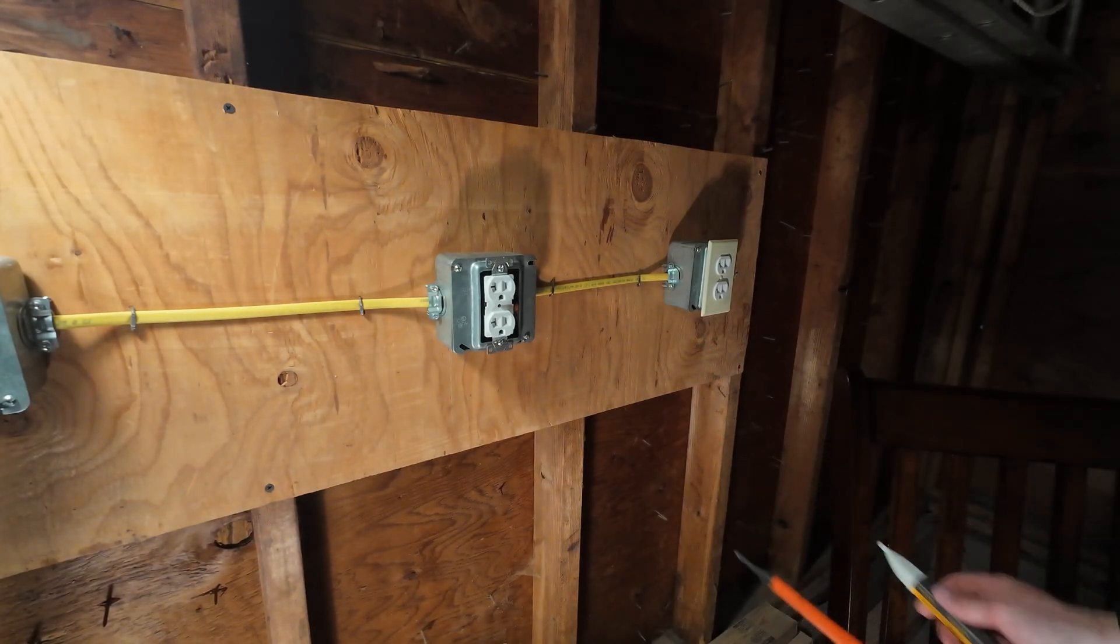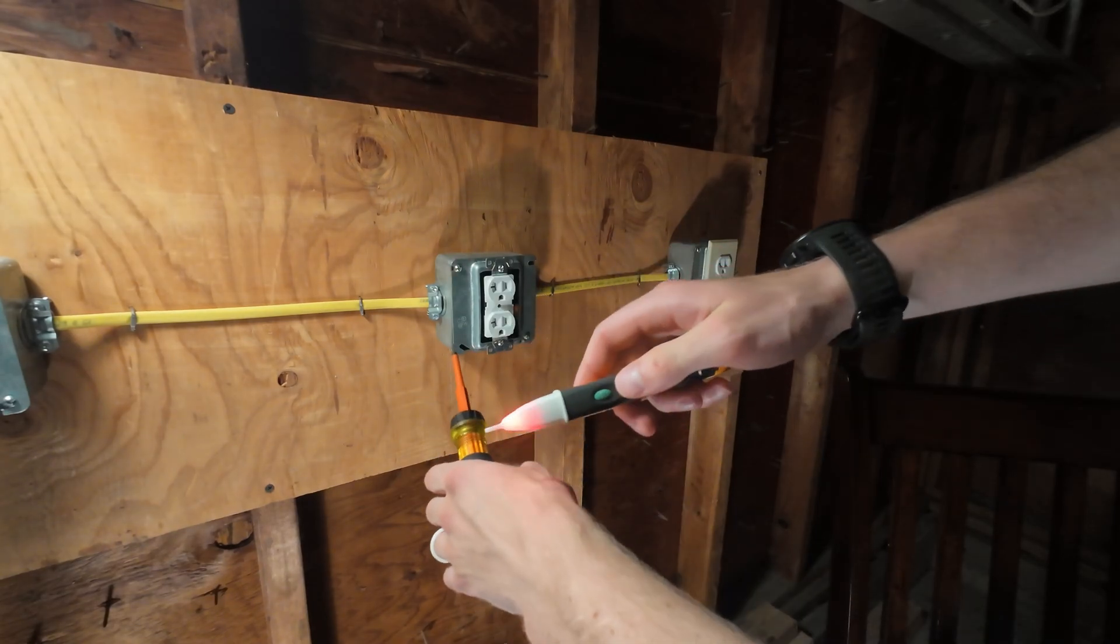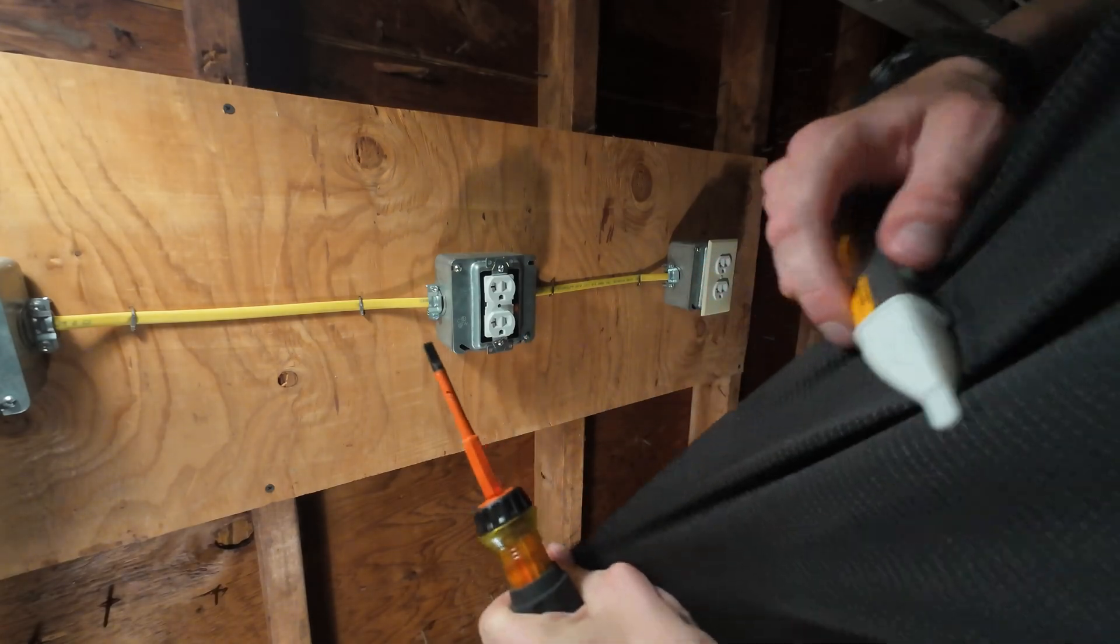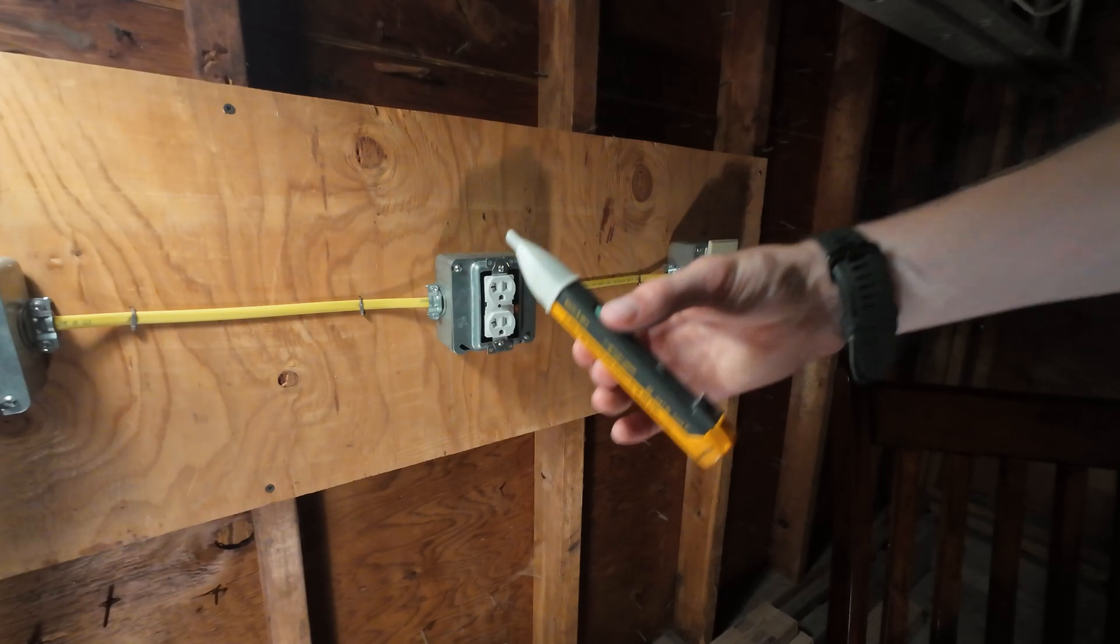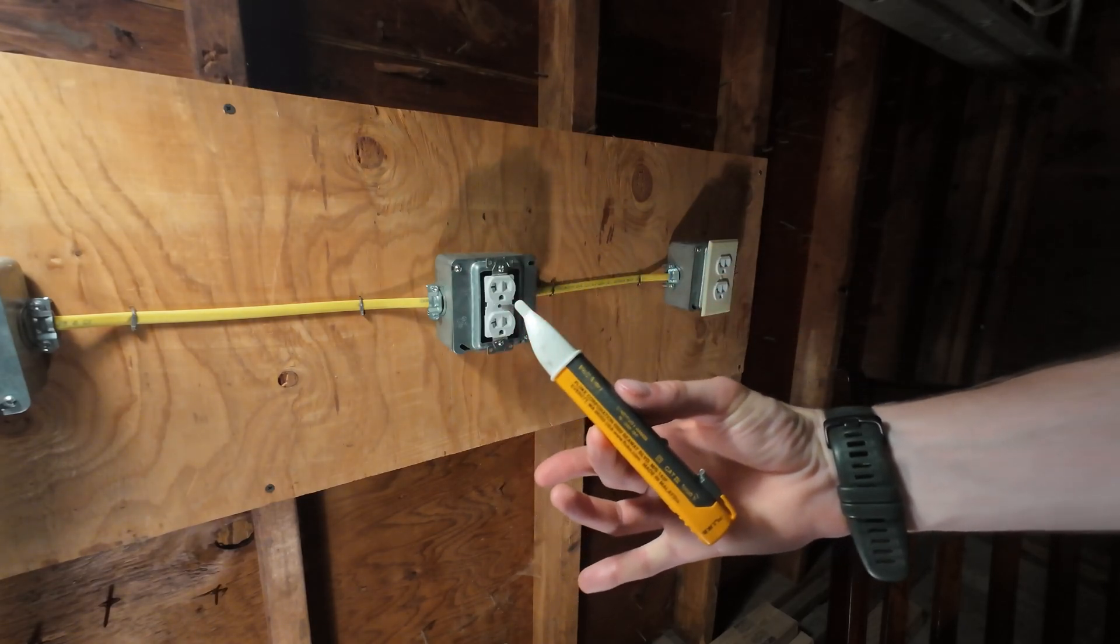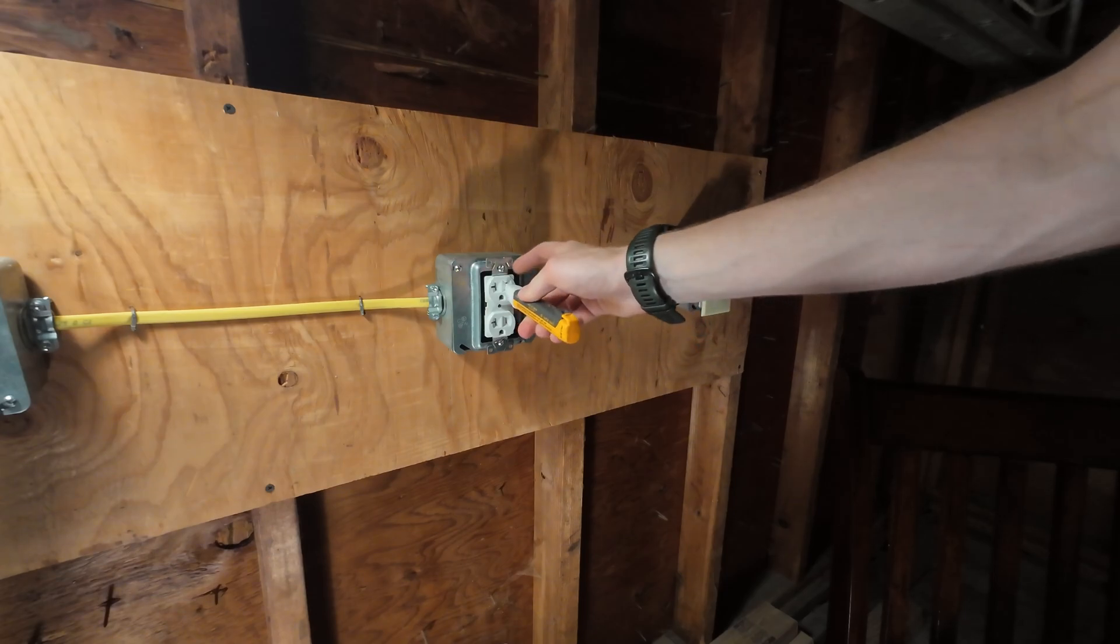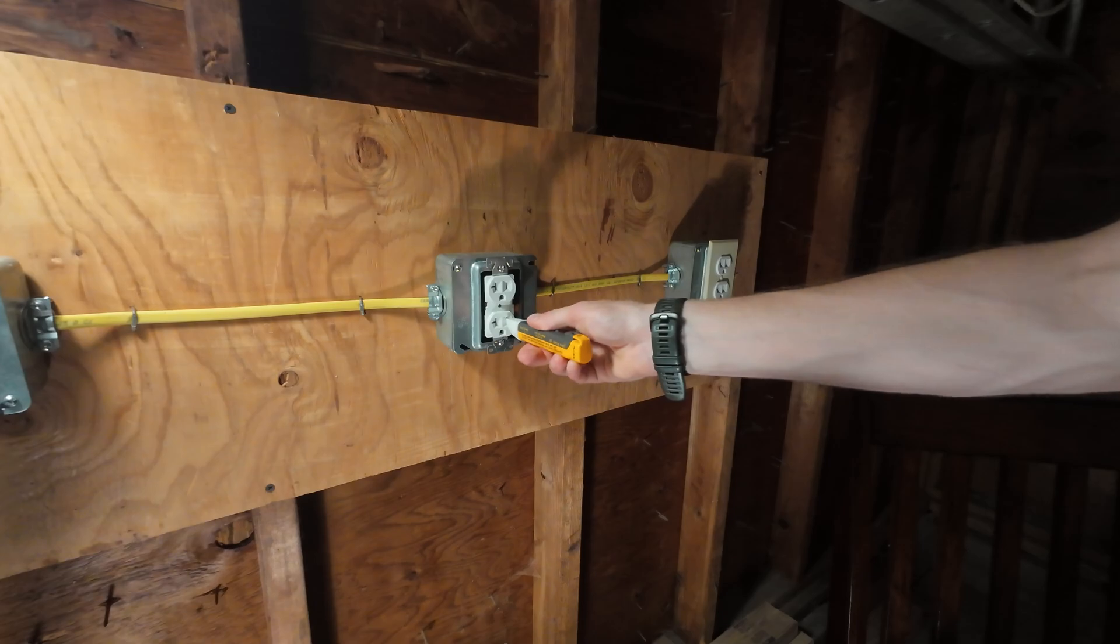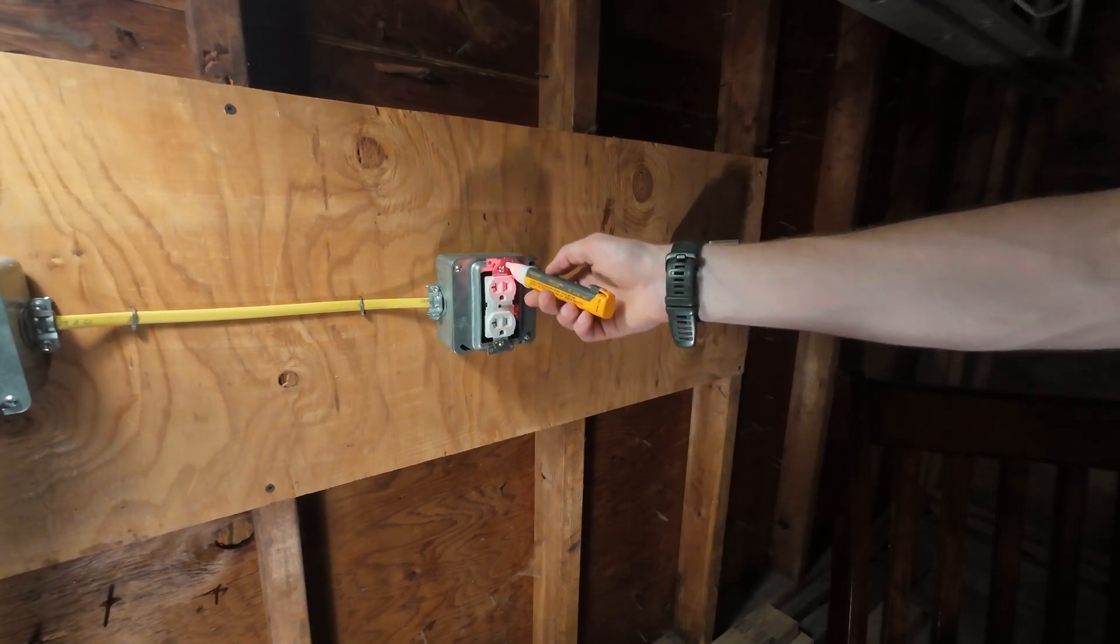Now you can use your non-contact voltage tester in this phase. One way to test it is it'll pick up static electricity. If you rub it against your shirt, hear how it beeped? That's one way to test it to make sure that this tester works. Next, stick it in the hot side, that's the right side. It's not beeping, not beeping on the side. So let's go ahead and loosen these screws up.